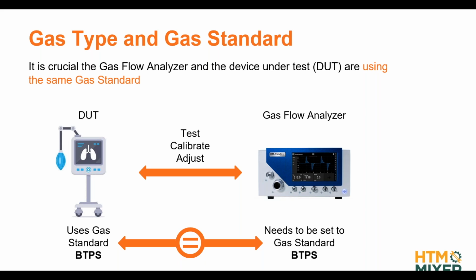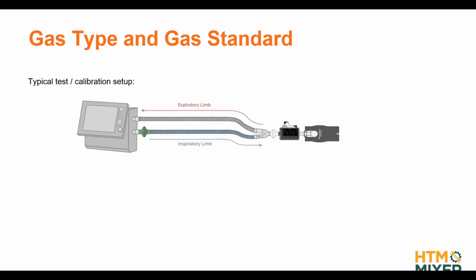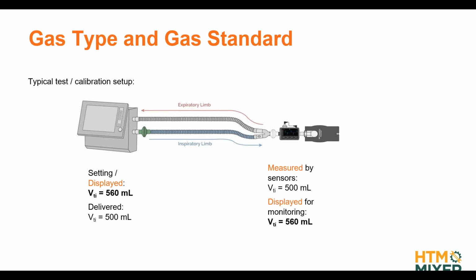So when we have the same gas standard used and displayed on our ventilator, and also on our analyzer, then it should match what is being displayed, even though the devices actually measure a lower volume. Because we have the same gas standard displayed, it should match with our volumes, because we are now comparing apples with apples, or maybe bananas with bananas. All right. Any questions about gas type and gas standard?